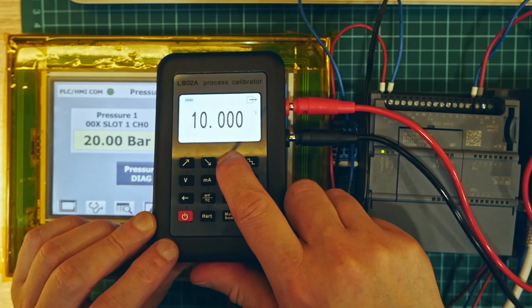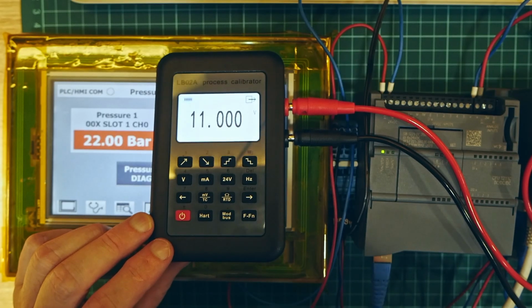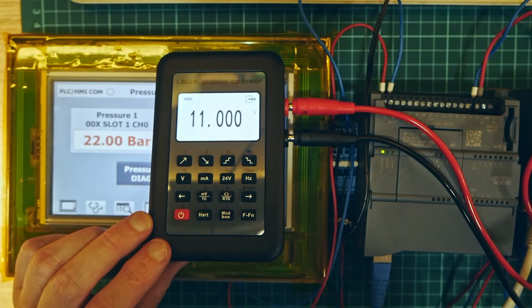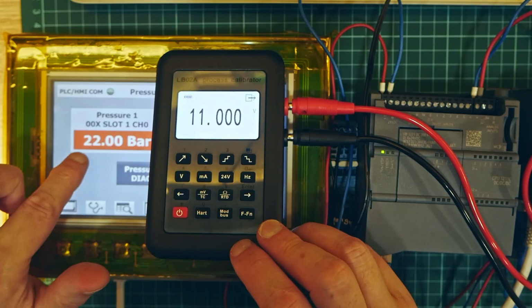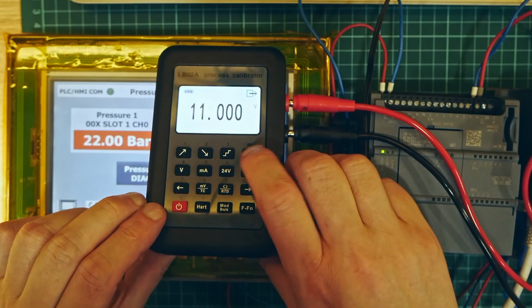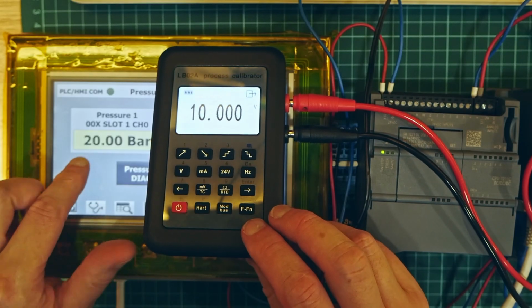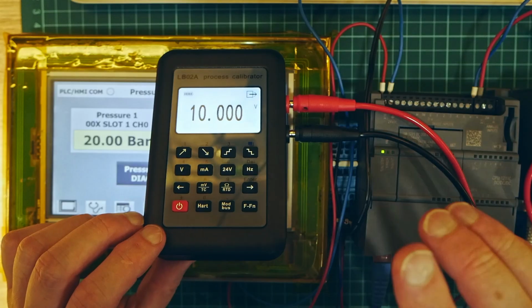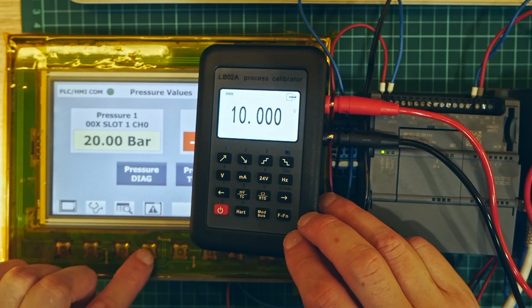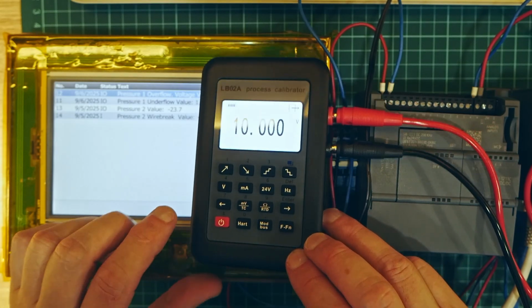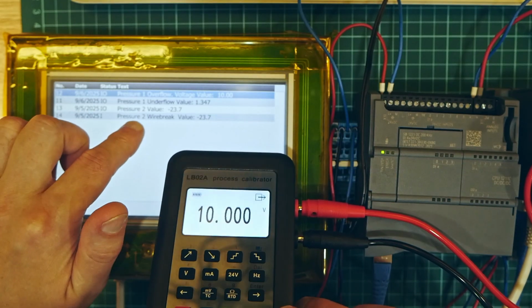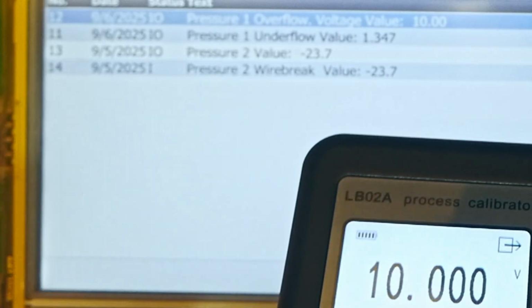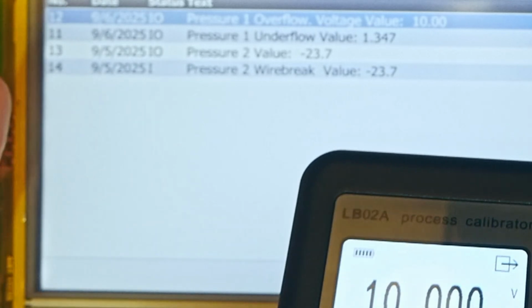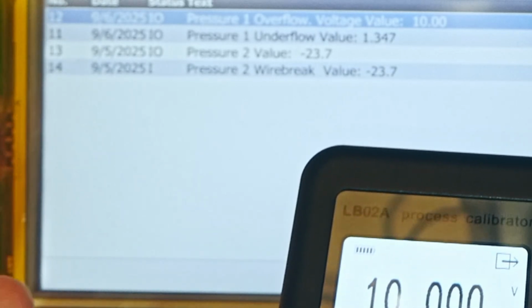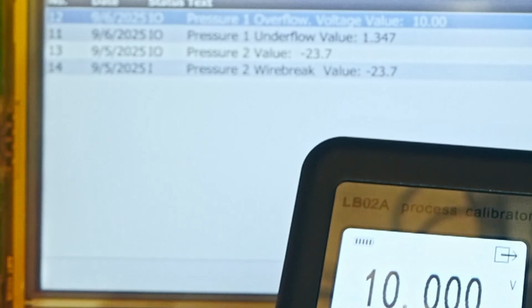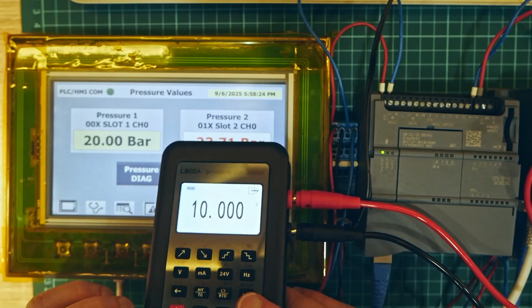And also, as I showed, we go to 11, so we go to overflow mode, over the limit. So we can simulate this for a short period of time. We will not damage the analog input card. With this we can also check alarms on our HMI. It will show alarm, it will stop process, it will work in an emergency case or not. So this is very useful.